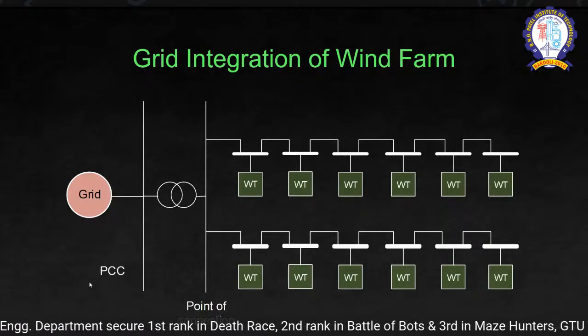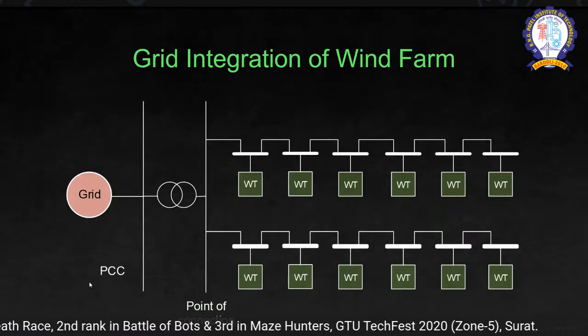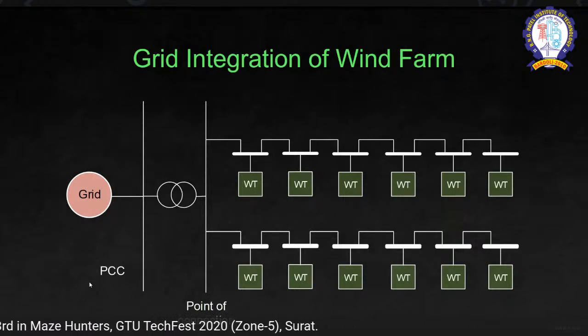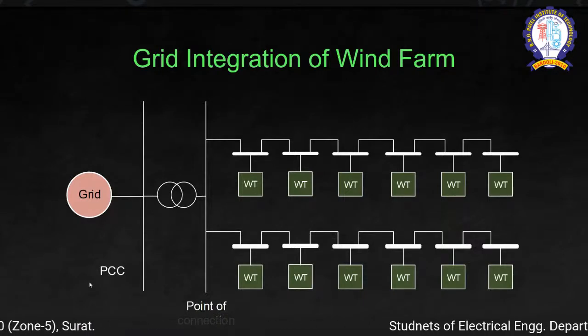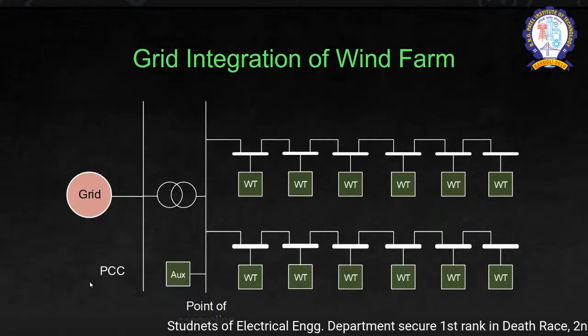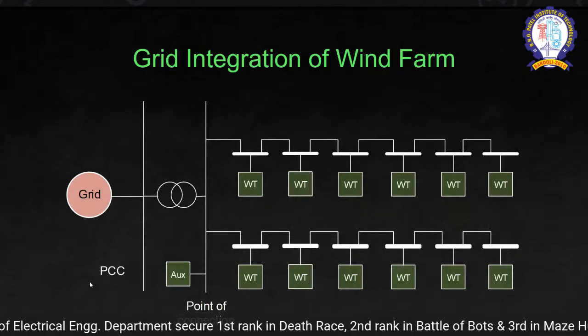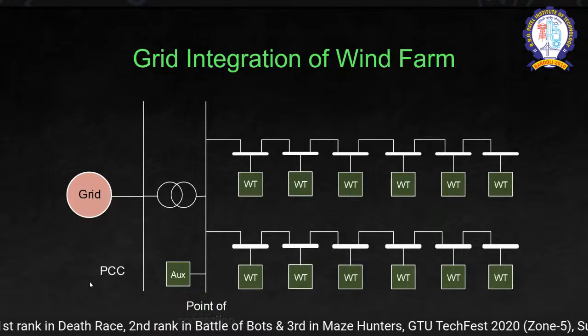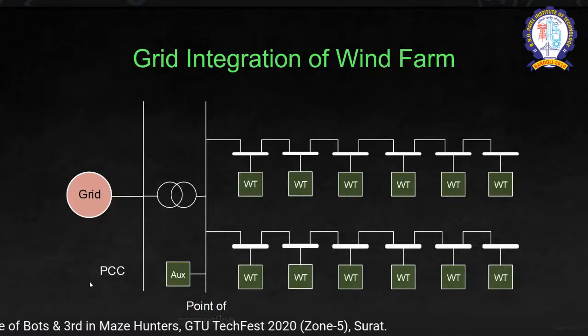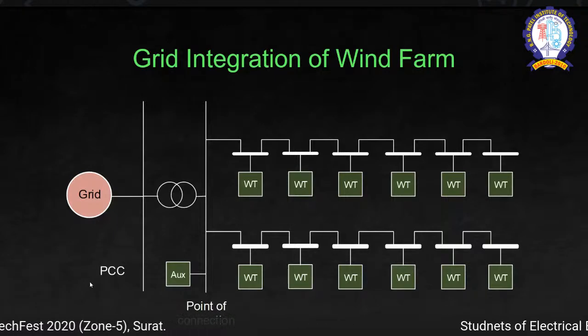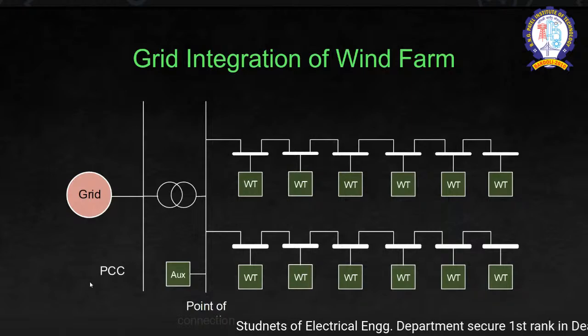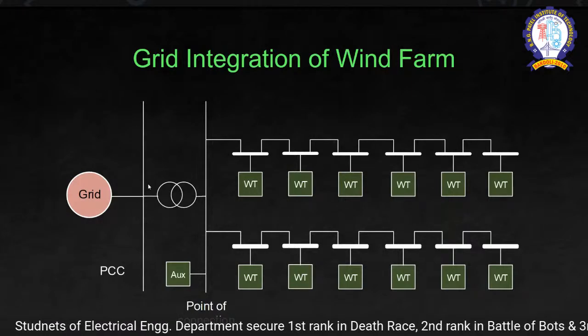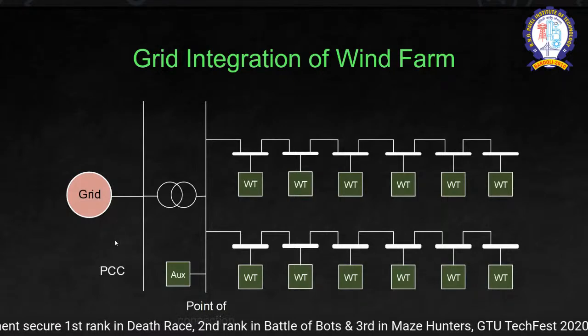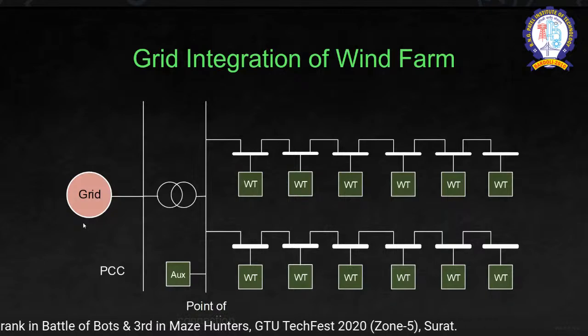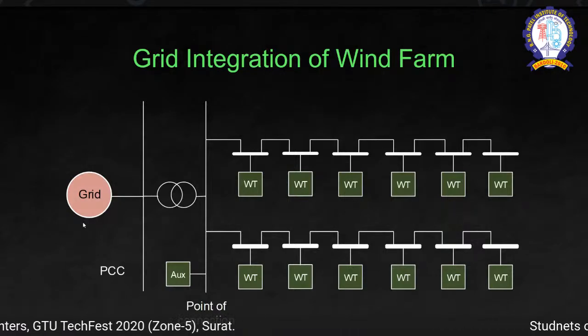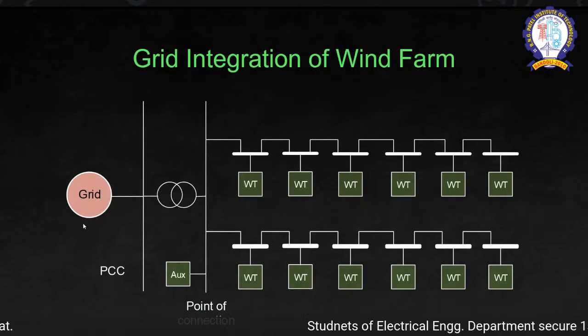Moreover, in the current state of the art, with advancement in electrical engineering, we have the incorporation of FACTS devices, or we can say SVC, STATCOM. So we need to connect an auxiliary active-reactive power mechanism, particularly a reactive power mechanism or FACTS devices, at the point of connection. At the point of connection, the power is controlled, active and reactive. Usually, we have an active power pumping mechanism to generate a higher amount of revenue, but the grid has its own power factor. So we need to produce the power at a particular power factor, because the grid does not always operate at unity power factor.